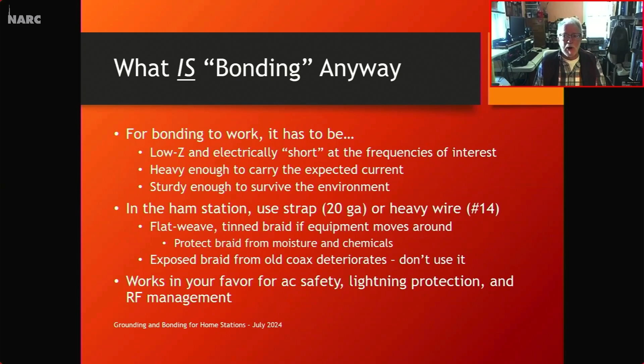If you want to use the braid from old coax as a conductor for this, just leave it in the jacket. Put a terminal on it at each end, waterproof it, and just treat it like a big wire. That's the way to use it. When you do this bonding correctly, use the right conductors, the materials, and all that, it works in your favor for AC safety, lightning protection, and RF management, all three.